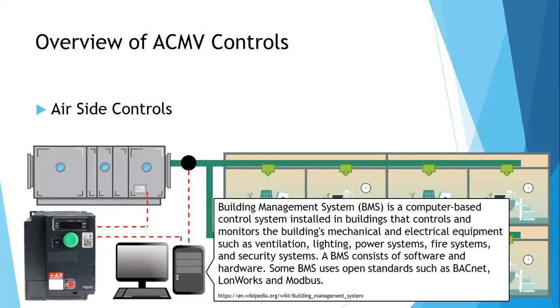This pressure sensor and this VSD are called field devices. So these field devices are the ones monitoring and controlling your equipment. These field devices are one, monitoring the conditions of your equipment, then giving these conditions to your BMS or your PLC. Then the control logic will evaluate these conditions and will send out an appropriate signal to other field devices so that the conditions for your monitoring devices are always met.